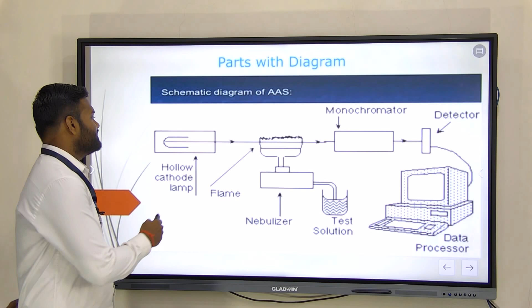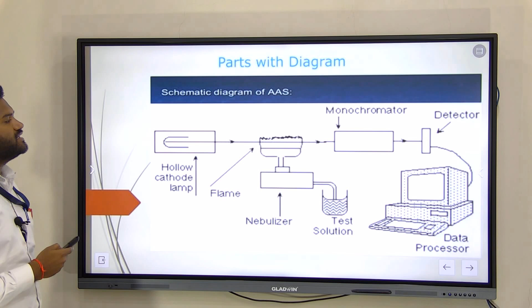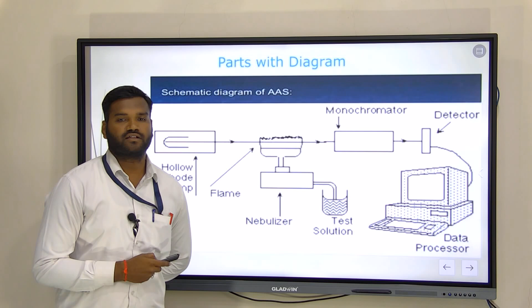So we can see the general schematic diagram of AAS. Firstly, this is the hollow cathode lamp which passes the light, and second is the flame nebulizer, where two types of nebulizer are used. Then there is a test solution, and next is the monochromator. After that, it goes to the detector, and last there is a data processor. We get the final outcome of the data in the data processor.